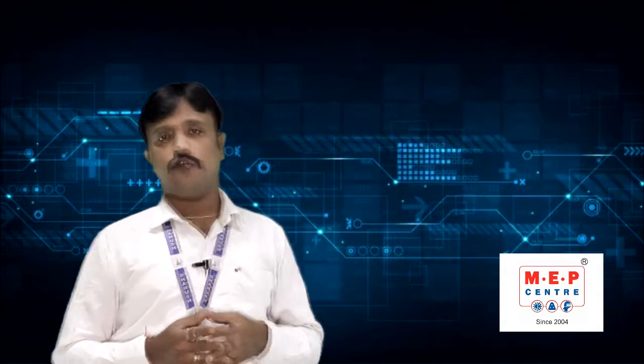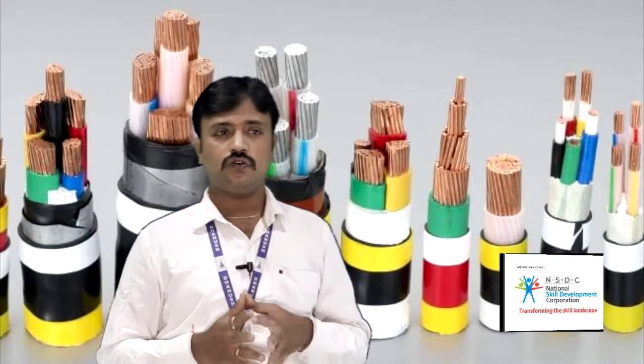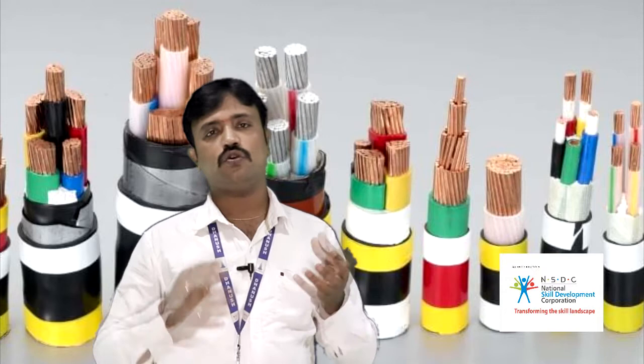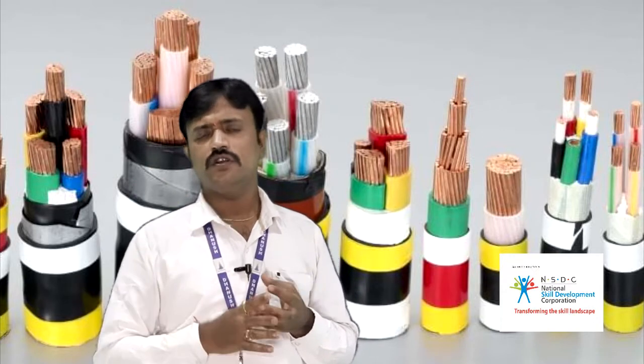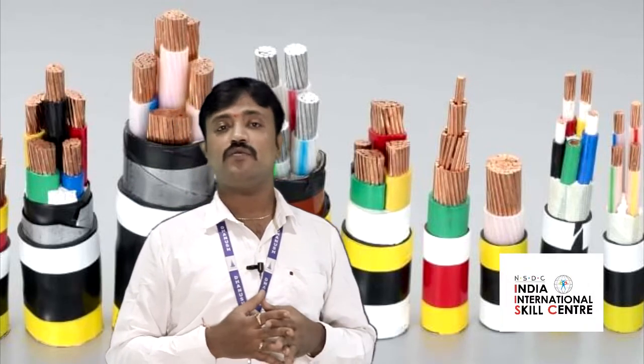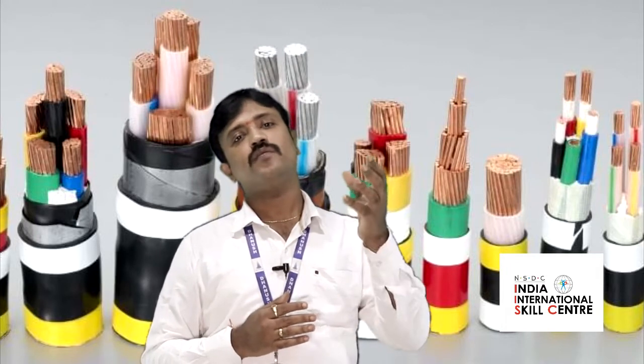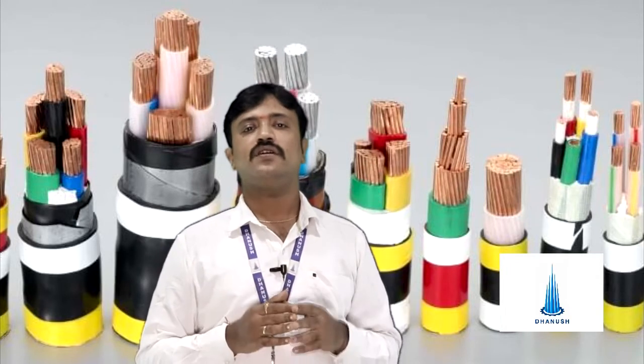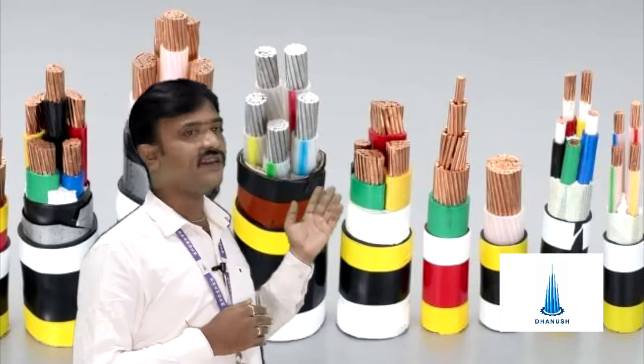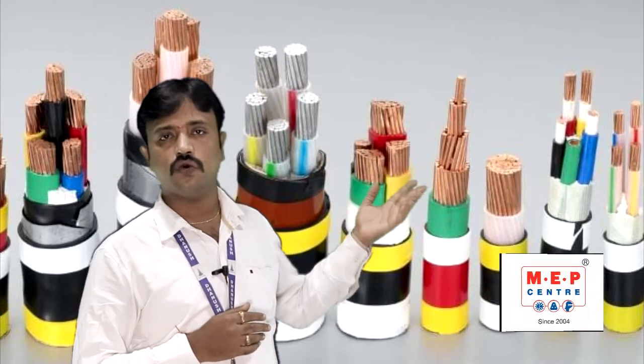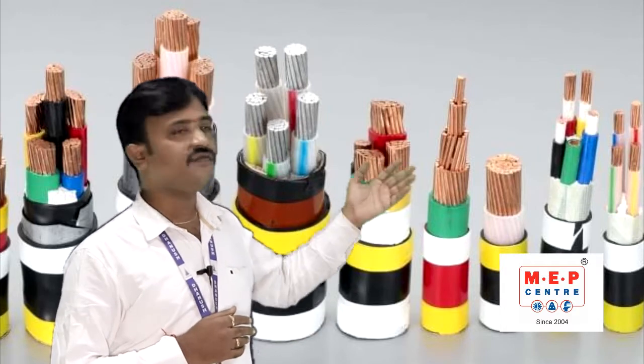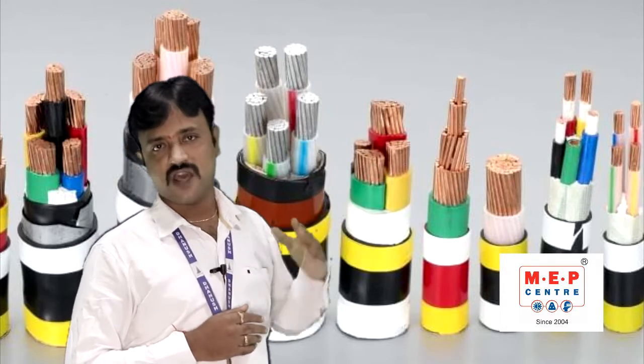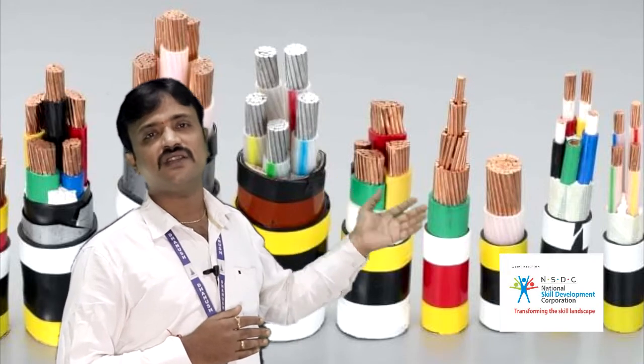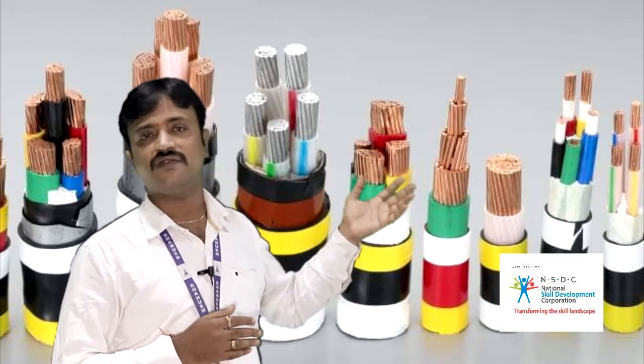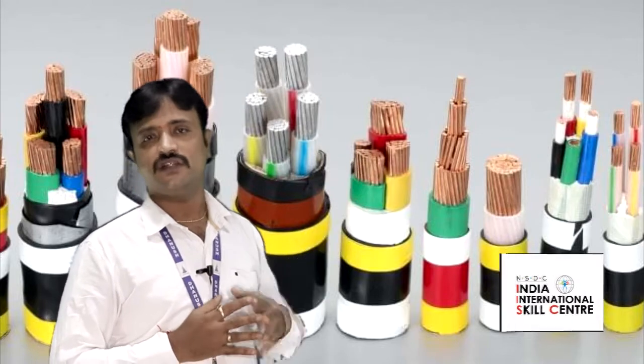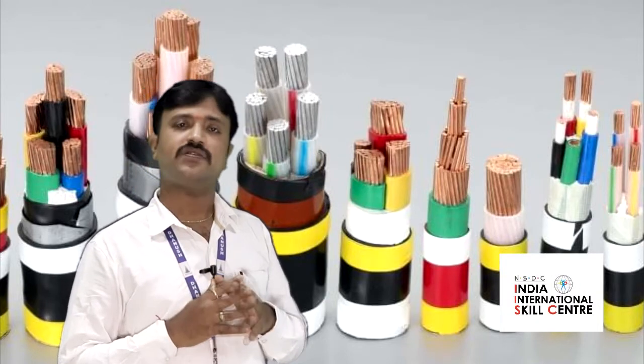Okay, now once you have defined the CT, the next step is to study the circuit breakers. But before the circuit breaker, let us know about the cables. To carry current from this transformer to all the loads of the building, we are going to put cables. When you're going with cable selection, people think it only depends upon the load current. No, cable selection depends on the load current, as well as we need to define the number of runs. When you see the cables, we have single core, two core, three core, three and a half core, and four core. So we are going to define the cores, the square mm size of the cable, and the insulation, which type of insulation we have, like PVC, HR PVC. So we are going to define that insulation, and the most important parameter is the number of runs.